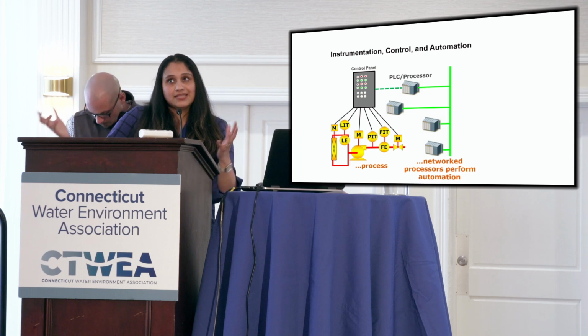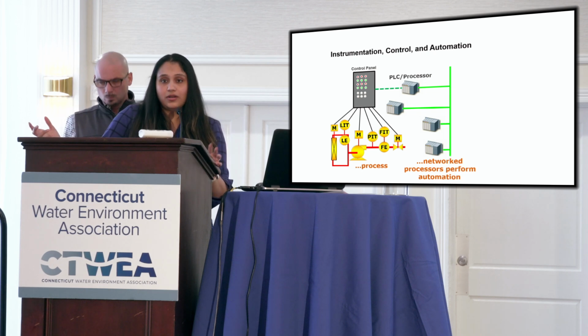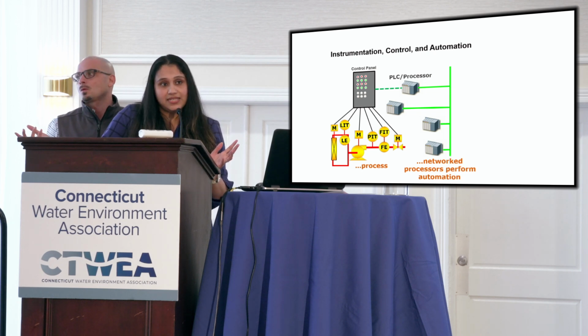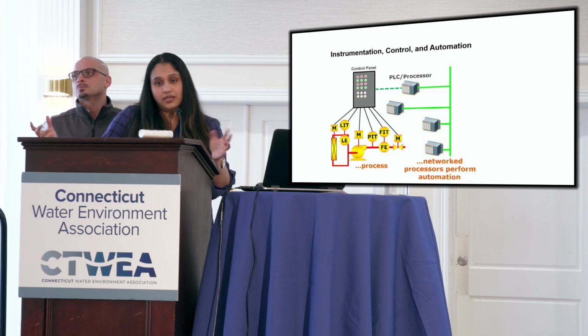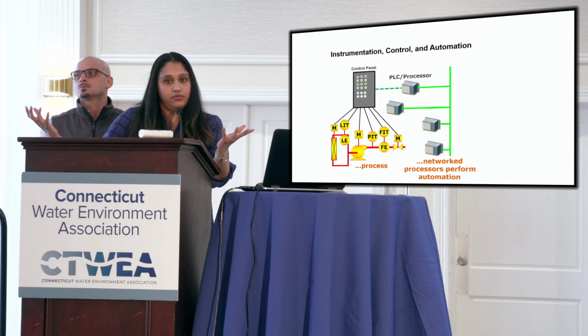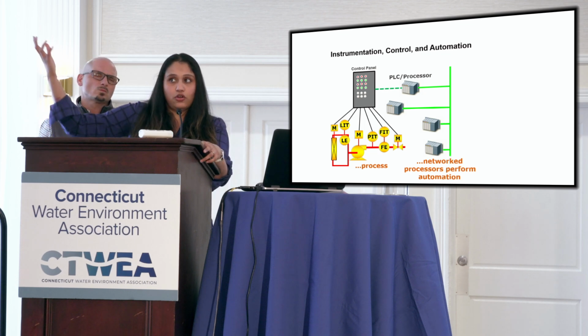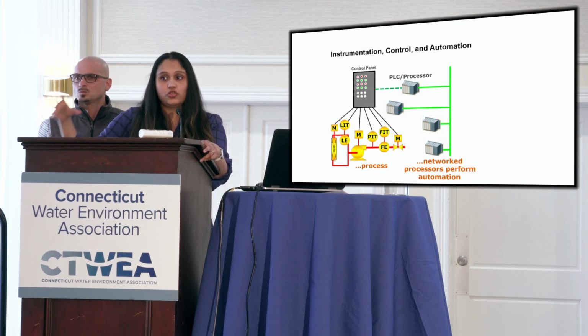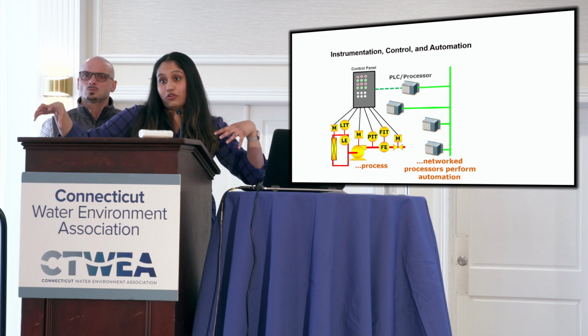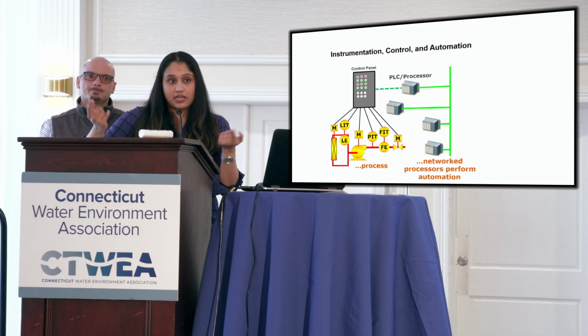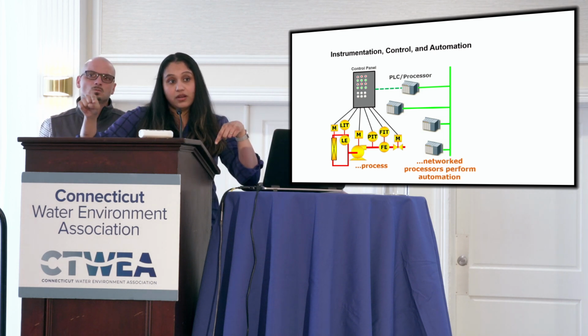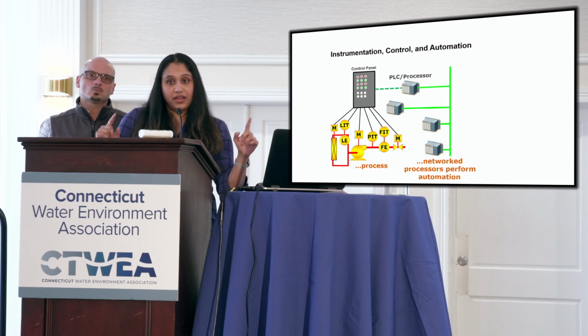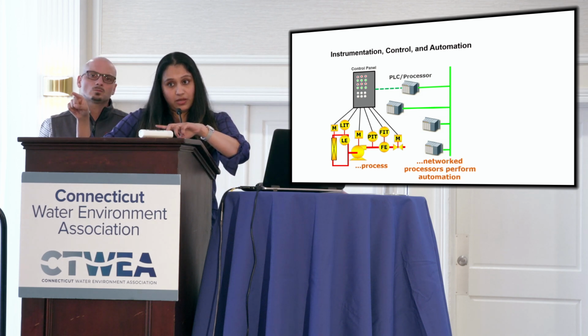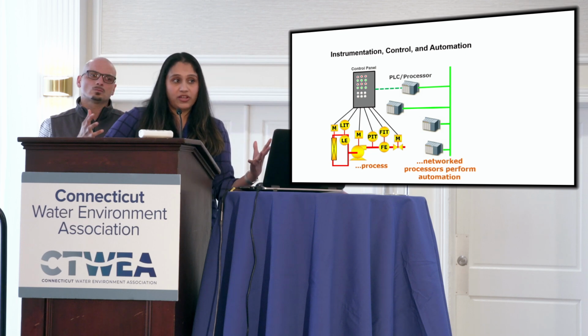As a design engineer, typical good practice is that each process area might have its own control panel with a PLC—your aeration tank system might have one, your influent pump station another. So you have various PLCs sitting across your plant, and everything is networked: the PLCs talk to one another, and finally all of that reports back to your HMI. All of this comprises your Scada system, not just the application you're seeing.